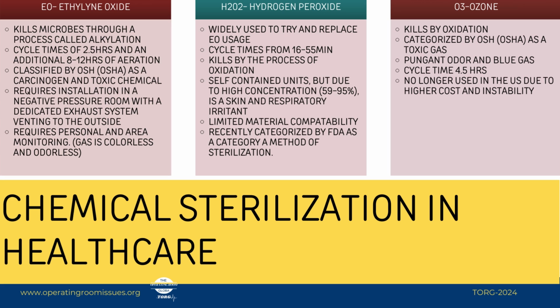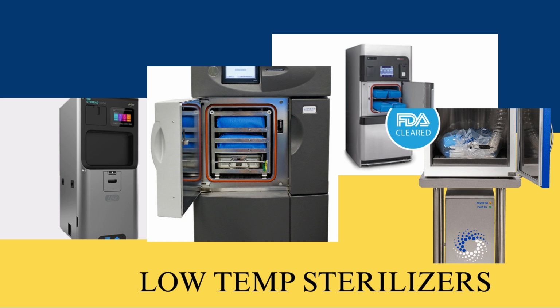At one point, we couldn't do it anywhere but in ethylene oxide, but that's a carcinogen, a cancer-causing agent. It's also known as a reproductive health problem. We can only run it on full loads, and the EPA in our government really strictly governs that item, so it reduces the greenhouse gases in the industry. This is just a few examples of the different low-temperature sterilizers in our facilities. To the left are the hydrogen peroxide sterilizers, the ozone sterilizers in the middle that we no longer use, and then we have the new FDA-cleared ethylene oxide sterilizers that, again, are very minimized in the United States as well.